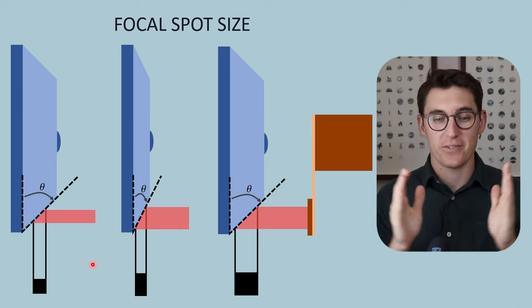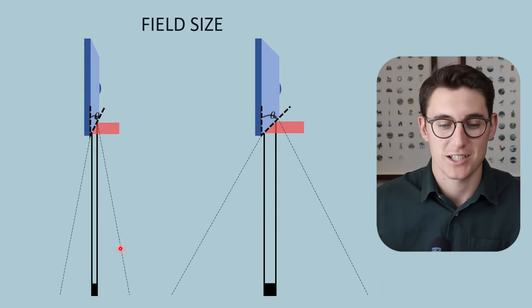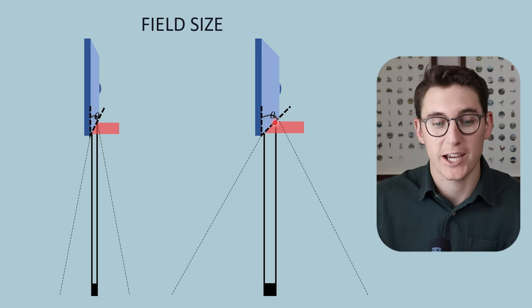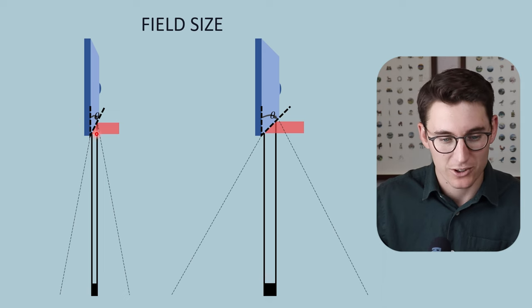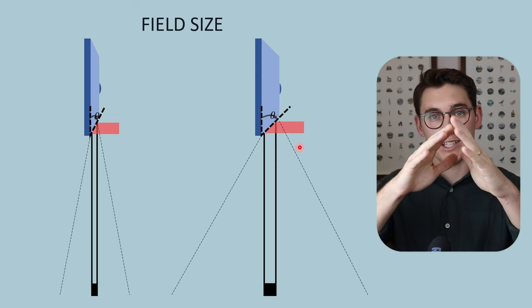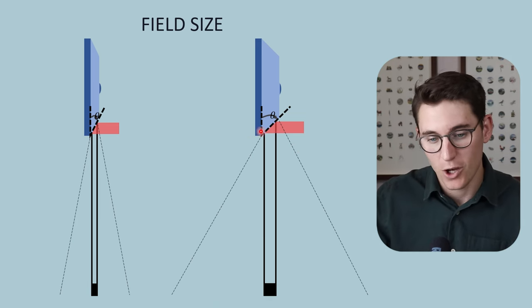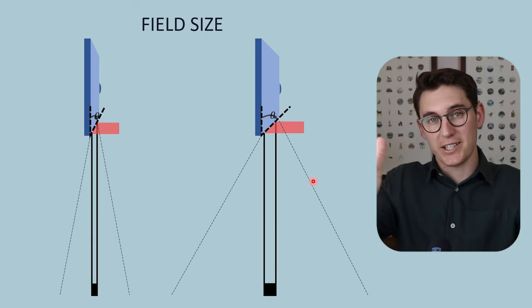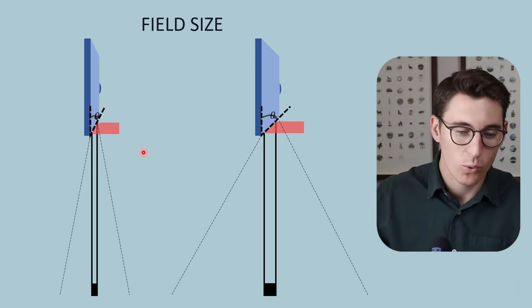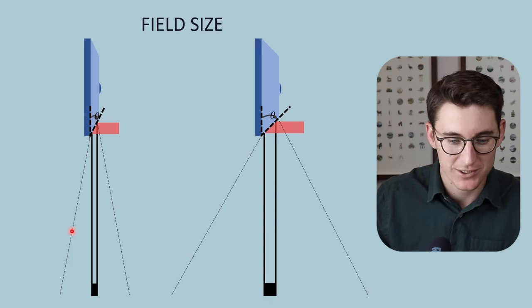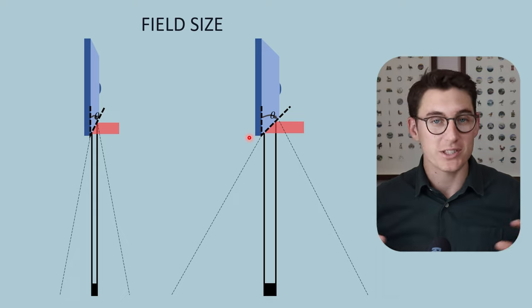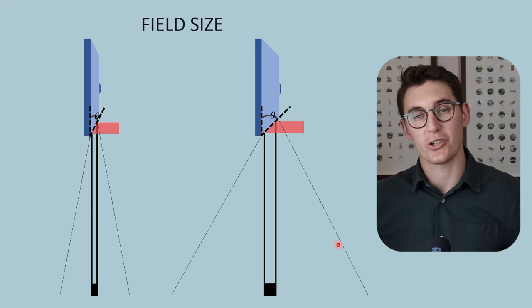Changing the anode angle also affects field size. With a large anode angle on the right and a small anode angle on the left using the same electron beam: the large anode angle gives a wider effective focal spot and larger field size — the area of x-rays heading towards our patient. So if we're imaging a large body structure like the entire abdomen, we may not be able to use a small anode angle because the field size won't be large enough, requiring us to increase the anode angle at the expense of a larger effective focal spot and more geometric blurring.